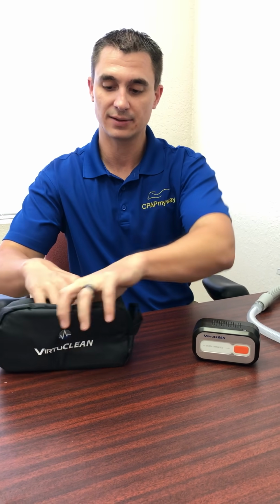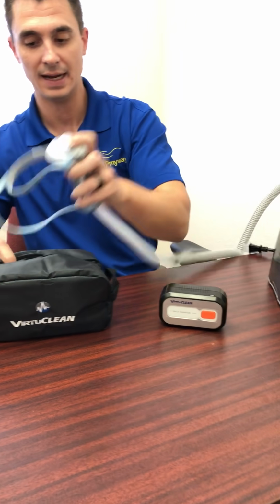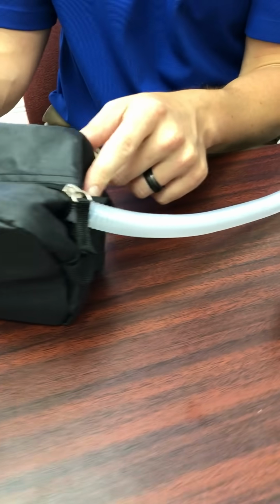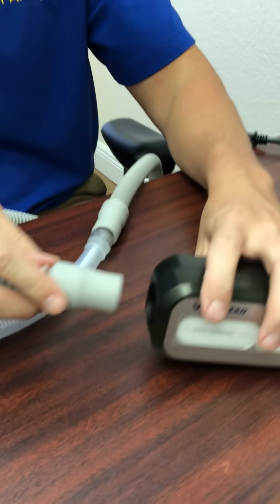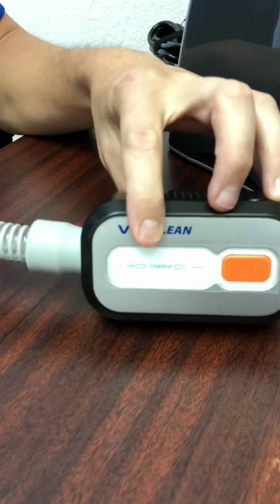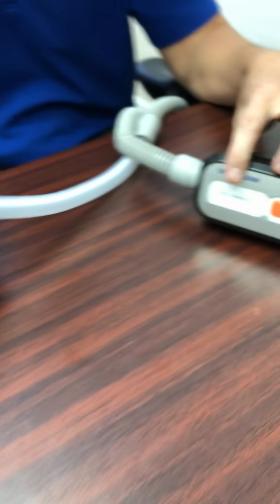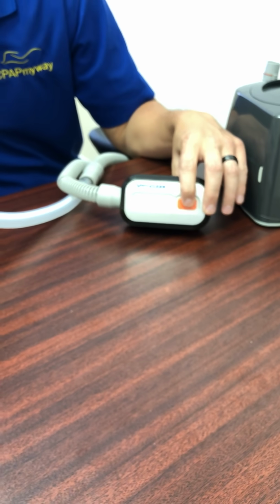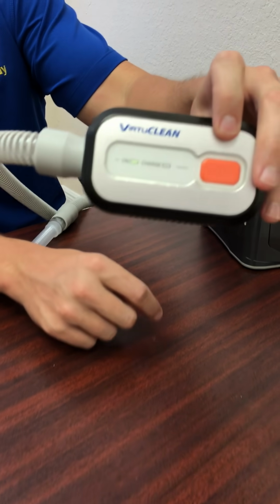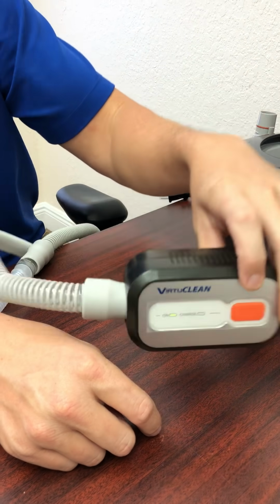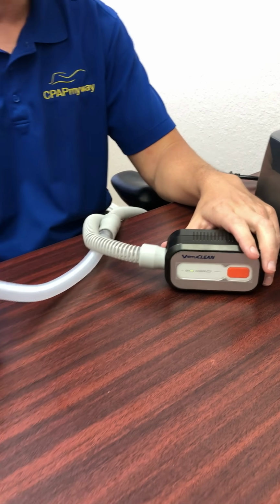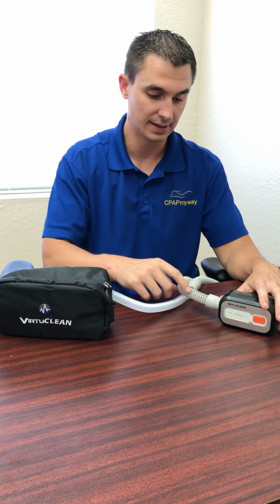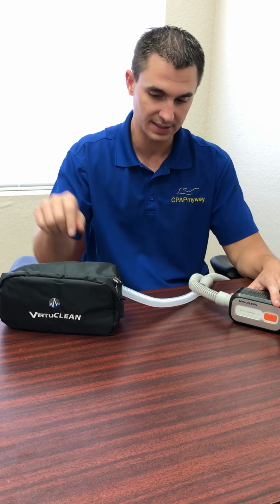The only thing you have to do to actually sterilize the mask is to drop the mask inside of that sterile bag, zip it up with the tubing hanging out. The next thing you'll do is grab the other side of your tube and remove it from the CPAP device itself and plug it onto the Virtuclean device. Okay? Now you've got a seamless system all the way through the mask. All you have to do then is press and hold the on button until it beeps. You'll notice there that the on light turns green. And you might hear it a little bit, it hums along. And it's going to push ionized oxygen through this entire system, where it will sterilize 99.99% of everything throughout the entire tubing and in and around the mask, since it's in the sterile bag.